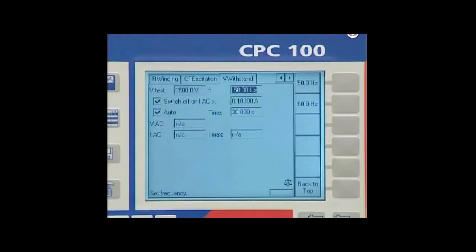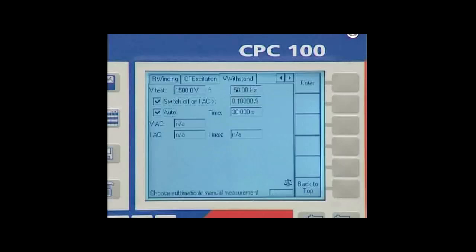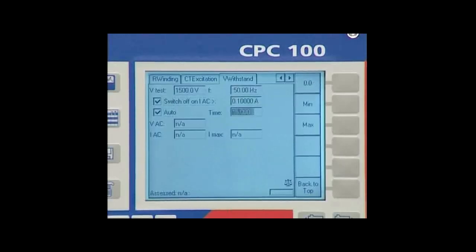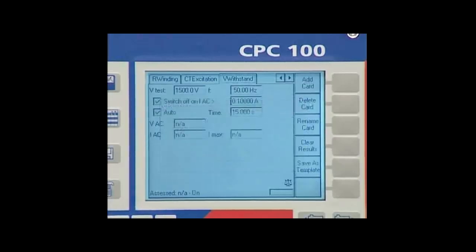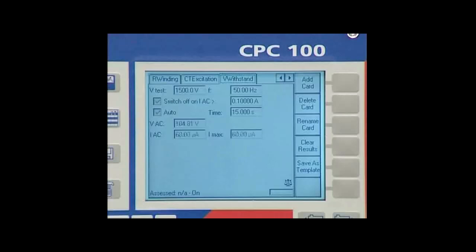We enter the amplitude of the test voltage and the test duration. The test will be stopped if the defined threshold for the maximum test current is exceeded. The measured test current as well as the maximum value of the test current that appeared during the entire test procedure are displayed.